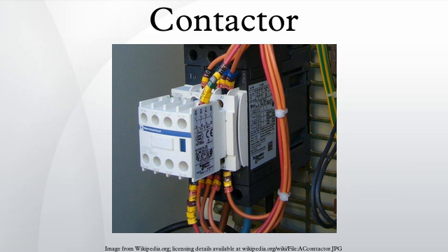Ratings: contactors are rated by designed load current per contact, maximum fault withstand current, duty cycle, design life expectancy, voltage, and coil voltage. A general-purpose motor control contactor may not be suitable for heavy starting duty on large motors. So-called definite-purpose contactors are carefully adapted to such applications as air conditioning compressor motor starting. North American and European ratings for contactors follow different philosophies, with North American general-purpose machine tool contactors generally emphasizing simplicity of application, while definite-purpose and European rating philosophy emphasizes design for the intended life cycle of the application.